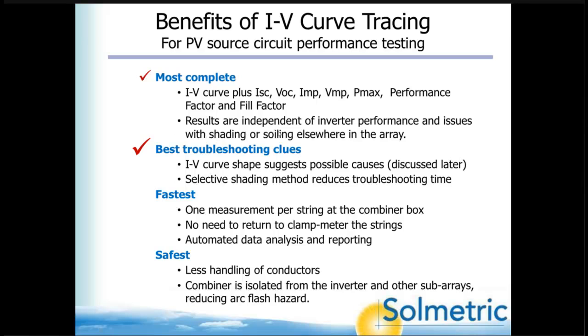If there's a cloud passing over some of the other parts of the array on that same inverter, you don't care about that. You don't care about the fact that the inverter is being pulled away from its proper max power point by that shading, because you're isolated. So the next really important benefit is that it provides really excellent troubleshooting clues.